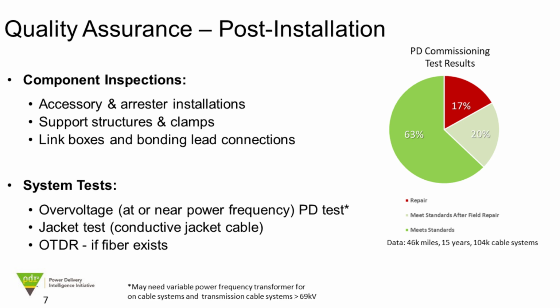So as Sharif said, all tests rely on the fact that they're going to tell you a condition of the asset, but if the asset is not going to be stable in that condition, for example, if somebody didn't rack a cable in a vault properly and it's going to fall down and yank on that cable and pull the cable out of the joint or misplace the joint, no test can predict what's going to happen in the future if the material is going to change. So we need stable materials by design, obviously, but also by installation.